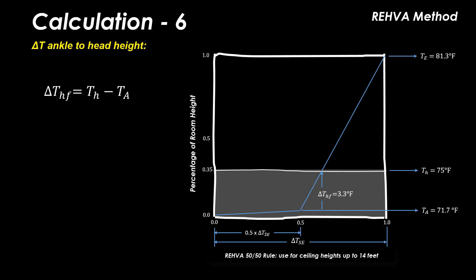To check that the temperature differential between floor and head height is within comfortable limits, simply subtract the ankle height temperature from the head height temperature, which is 3.3°F. This is well below our target of 5.4°F for seated occupants.